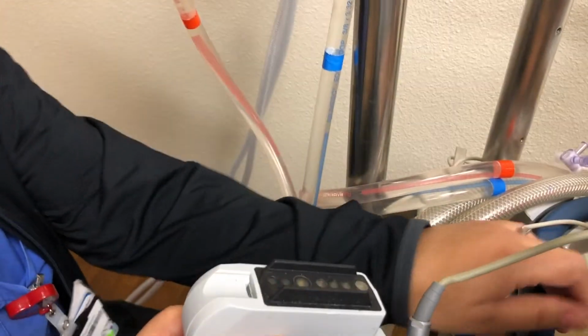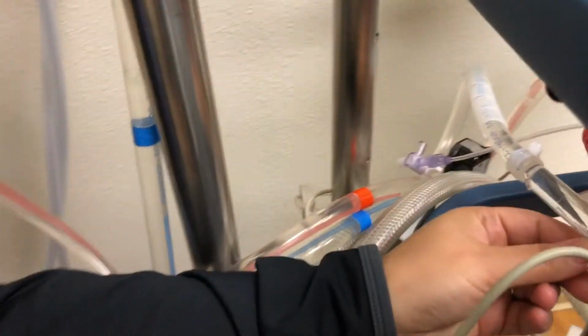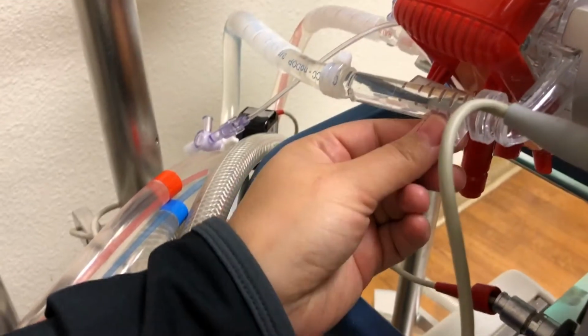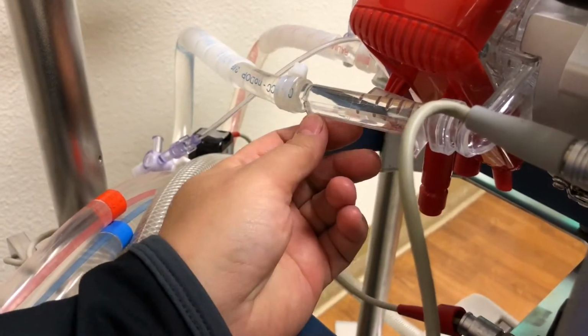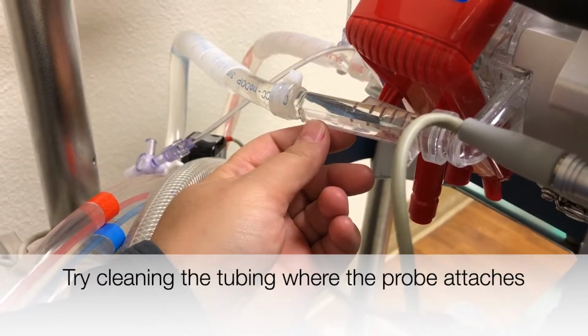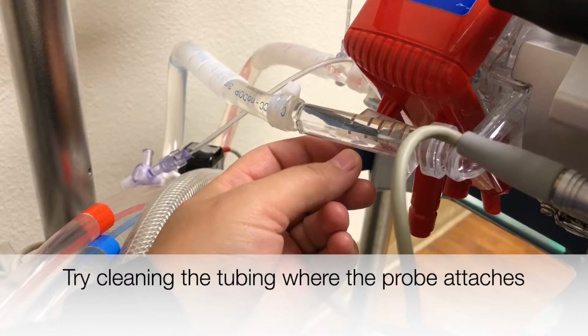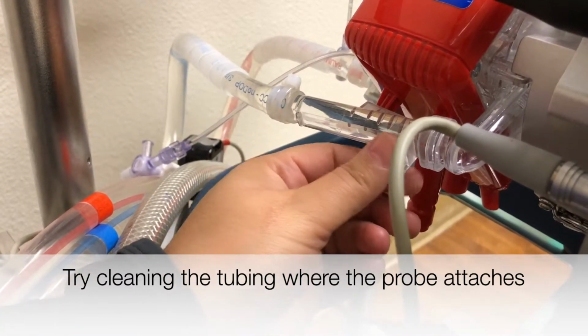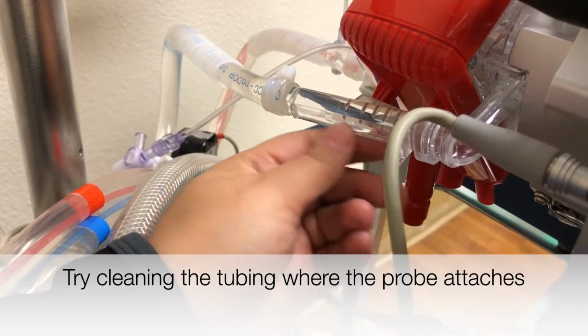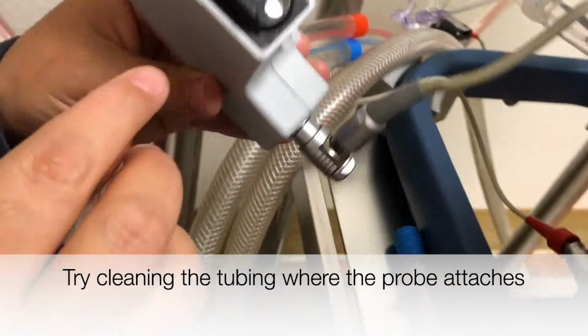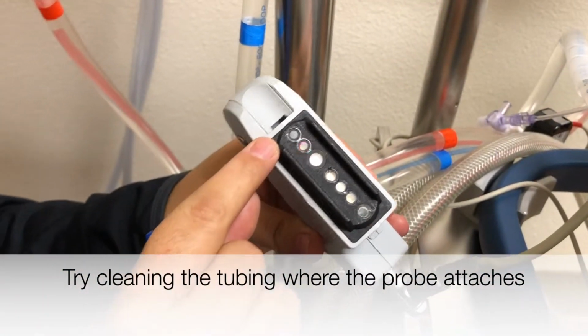Or on your disposable part, which is sitting right here, there could be blood on it or dirt on it, and that can also affect your values. So my first recommendation would be, if you know the patient is not desatting, to take an alcohol wipe and make sure this disposable part is completely clean. I would even take an alcohol wipe and clean this area right here and put it back on and see if that's going to help.